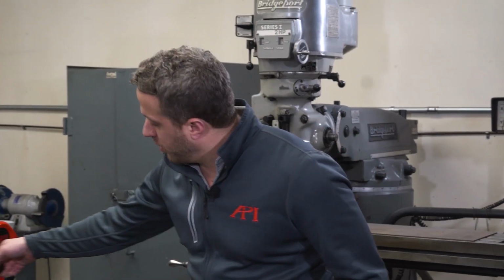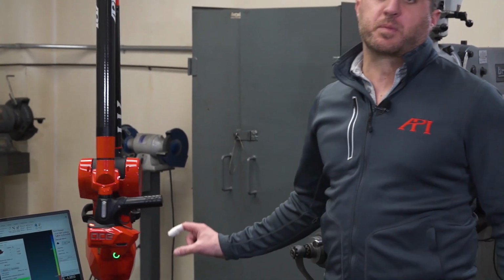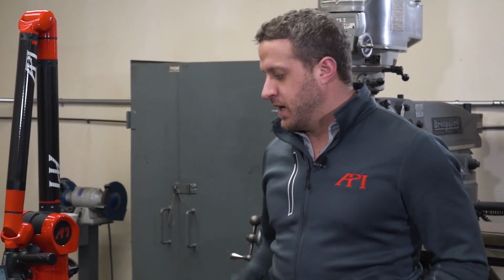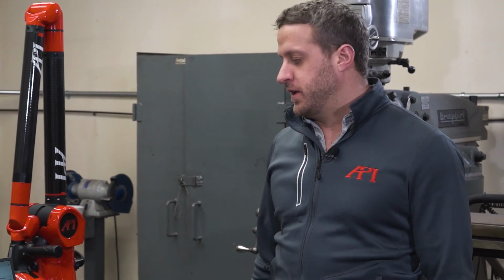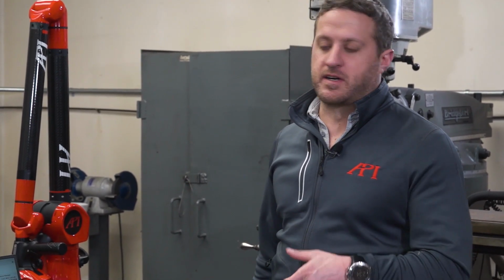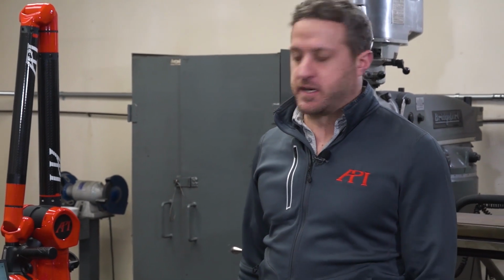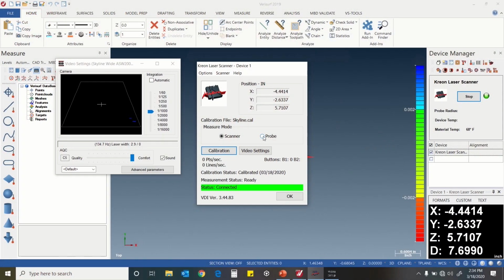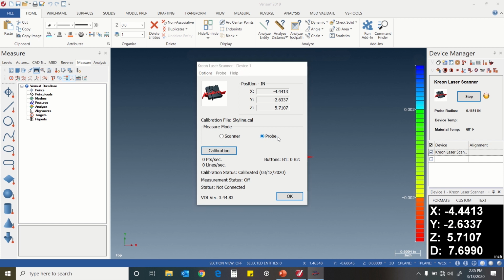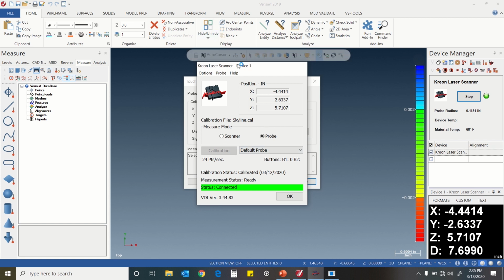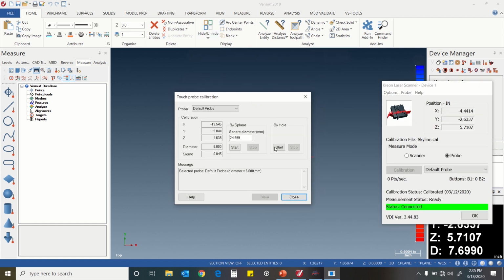So now that we have the probe installed, and this is kind of a shorter probe, but you can put longer ones on it. The longer probe that you install on it, you'll notice you'll probably get a less tight calibration on it. We're going to switch over to probe. Then I'm going to hit calibration. So I can actually put in my sphere. So I'll put in this sphere, 24.999, and I'll hit start.